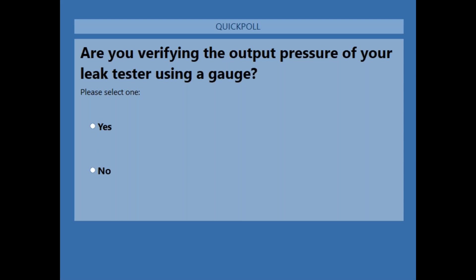Okay, great, thank you. So for the 60% that say no, what happens if you don't test that? These are some of the scopes that go back to the service area. If you don't have a leak tester that puts in enough pressure, you could actually flood your scope. This is one of those scopes that went to the repair center, and failing the leak test was not one of the issues mentioned. But when they open it, you can actually see that the scope is flooded. Obviously, the scope gets damaged, and the other issue is that cross-contamination of the patient is going to be a problem. So it's really important to verify that your tools are working effectively.